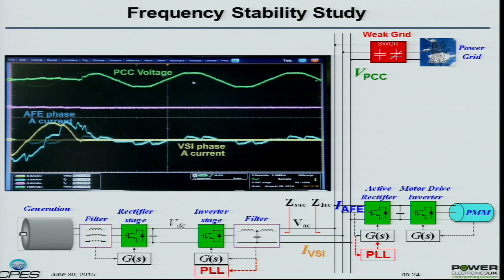At one point this one comes on, and you'll see everything becomes sinusoidal and works well. These are the two currents, one coming from here and a small current from the grid. But in real time, they eventually desynchronize. What's happening is that this PLL tries to synchronize to the other one, to itself, and to the grid, and the other one does the same, and eventually they can't decide whom to synchronize to.